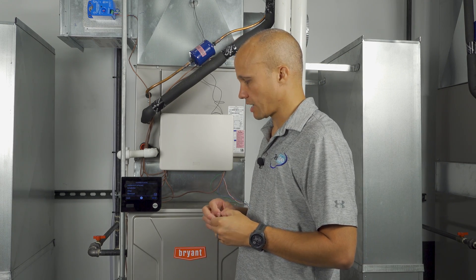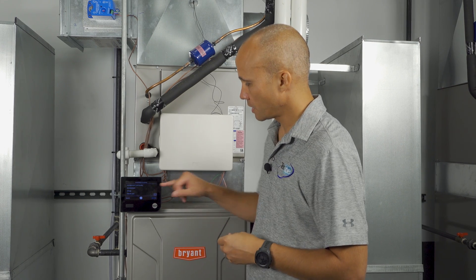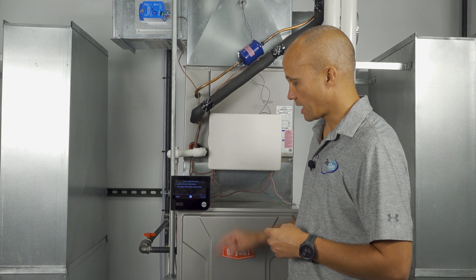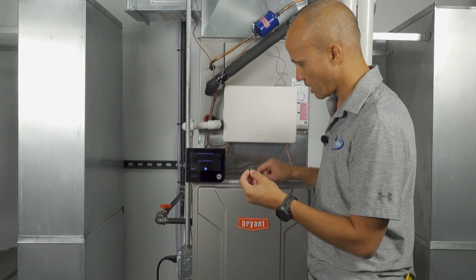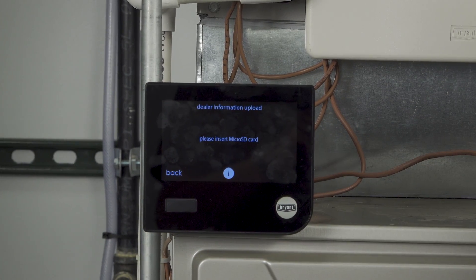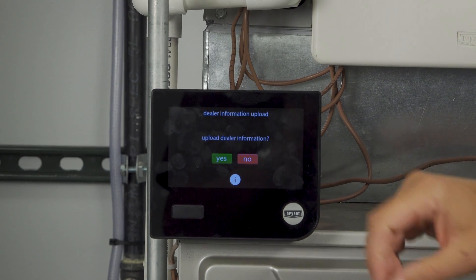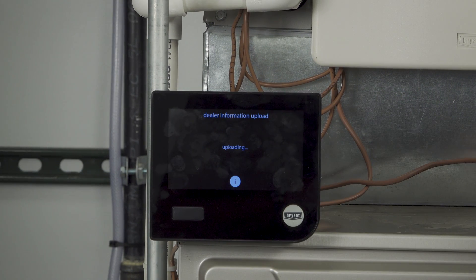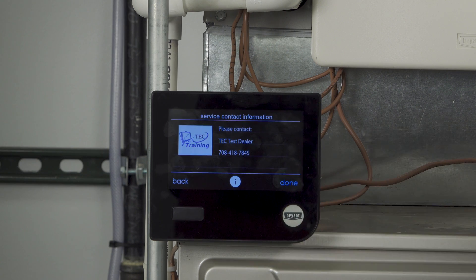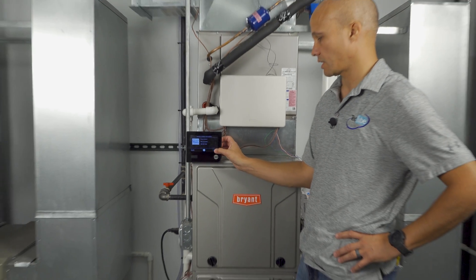I already have the thermostat pulled up to the dealer settings. Scroll down to where it says Dealer Contact Information and press it. Select Upload Dealer Information — it's going to ask for the SD card. Insert it into the bottom of the thermostat all the way until it clicks. It should pull the data from the card. When it asks if you want to update the info, say yes. It will pull out the logo and contact information including the phone number. It says successful — hit Next. It gives you a sample of what it'll show: in this case TEC Training, TEC Test Dealer, and the phone number. In your case, it would be your actual dealership. Press Done.